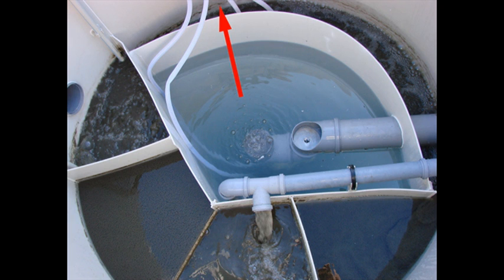The blower comes on and off in 15 minute increments over a 24 hour period. Finally, the effluent flows into the separation chamber where the sludge settles and drops to the bottom for redistribution, while the treated effluent rises to the top and is piped away to a percolation field, or in some cases to surface waters when given a discharge license.